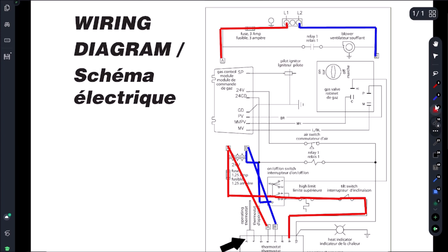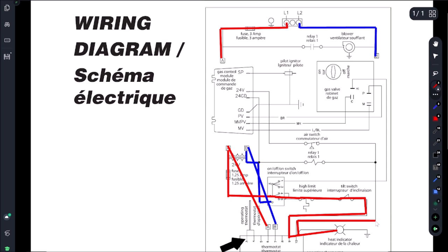What happens at that point once we get a call for heat, it'll actually jumper it to here. So 9 and 10, imagine this is a little switch, we'll jumper up to here, we'll get our heat indication light which we saw, and number 10 is going to bring it up first to our relay coil which we'll revisit in a minute, and we're going to come through this combustion air switch. So what closes this combustion air switch?